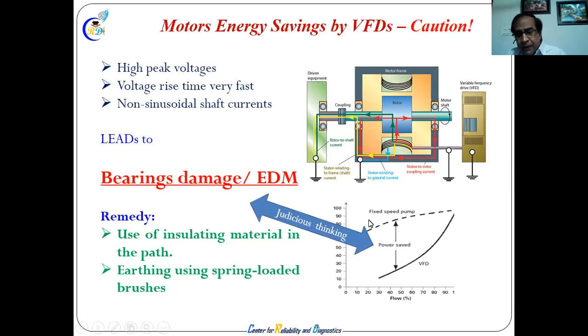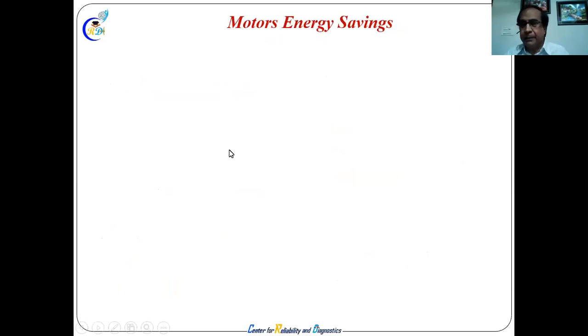See, in a fixed speed pump like this, and with a VFD like this, we save this much, but this much saving should not create a problem for my motor itself. If it is an HT motor, 1 megawatt, 2 megawatt, plenty in power plants, mainly in steel plants and process plants, a 1 megawatt machine, because of bearing damage and entire shaft broken, it will be crores of rupees of production loss. So while saving energy here by VFD, you may damage the entire machine. We have to be a little bit cautious.